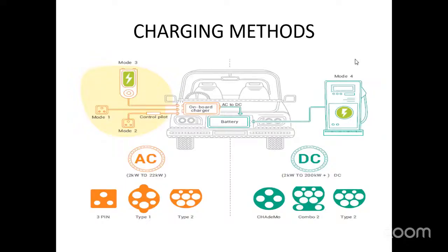The main components available in this charging method include four modes of operation, the onboard charger which converts AC to battery power, and some connectors. Mode 1 and mode 2 are applicable for connecting an EV to a standard socket outlet using a cable and plug. Mode 1, also known as dumb charging, permits no communication between the EV and EVSE, and its use is not recommended. The portable cable used in mode 2 has inbuilt protection and control capability and is typically used for home charging. Mode 3 and mode 4, which provide a separate charger device to supply power to the EV, have improved control systems and are used for commercial or public charging.